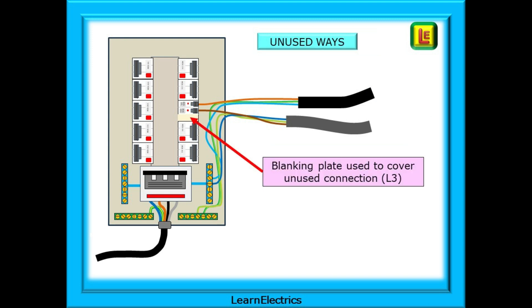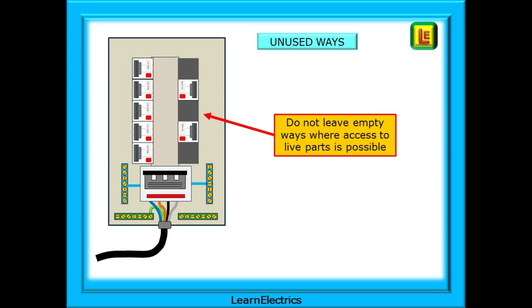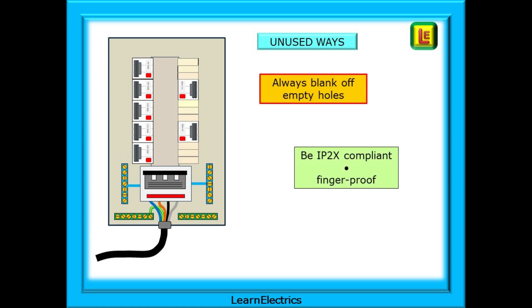In this example, we are not using the L3 terminal. So, we must blank the hole off in the cabinet cover to prevent access to live parts. We must do this with all unused ways. We do not leave empty ways where access to live parts is possible. Always blank off empty holes so that we are IP2X compliant. IP2X is finger-proof. Objects greater than 12.5mm cannot get into the cabinet and touch live parts. A dodge that many electricians will use if they don't have blanking plates is to put an unused circuit breaker into the hole and leave it switched off. Far better to do that than to leave an open hole.